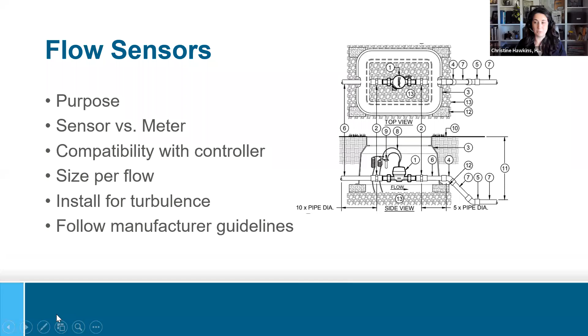Next slide. Thank you. So this detail is what you would see on a plan set available from manufacturers. It shows the top and side view of a flow sensor installed inside a valve box below grade. But see the notation down on the bottom, it says 10x and 5x. This is the amount of pipe that is unobstructed and uninterrupted that is installed upstream and downstream of that flow sensor body in order to reduce turbulent flow through the flow sensor chamber. We want that flow going through nice and smoothly so that paddle wheel can get a good clear read. This way the sensor can get good clean data to send to the controller.